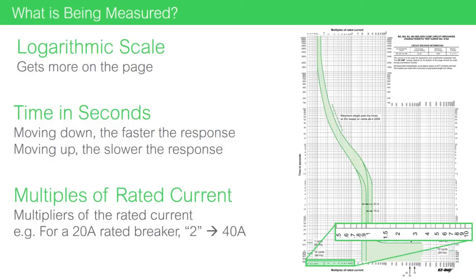For instance, if this time-current curve was reporting the characteristics of a 20-amp circuit breaker, 2 would not mean 2 amps, but 2 times the rating of the circuit breaker, in this case, 40 amps.